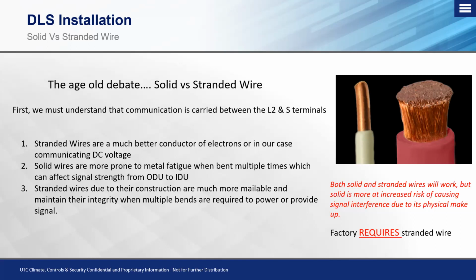Okay, both solid and stranded wires will work. It's not that solid won't work, but if we have an application where we're going to be feeding power wire through multiple different bends, or we're snaking it through different areas, stranded wire in that application is going to be the best suited, just because of the solid wire's physical makeup. The more bends you have in it, the more risk you have of actually cracking the wire, cracking the copper, and essentially causing a signal interference. So it's not that solid won't work, it will, but stranded is much more malleable and much easier to deal with, especially with the ductless applications on how we're routing the power wire. Okay, so don't think that solid won't work, because it will. It just depends on application, and more importantly, the factory does require 14 gauge stranded wire.